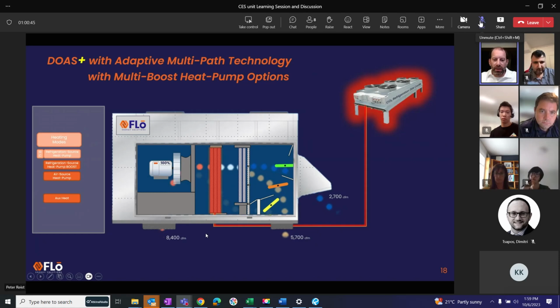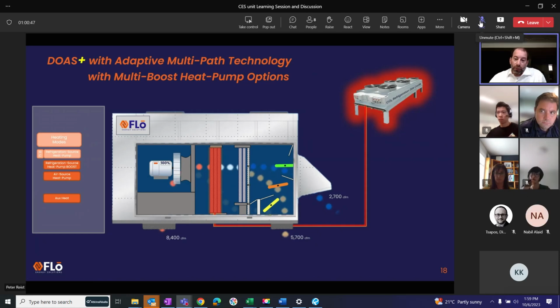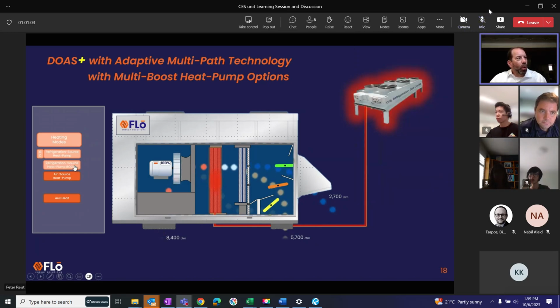It might still be, even in this project, a first stage of heating, because it's okay on its own. But what happens often is, in some of our systems, you guys will do some CO2 projects with other customers. I know Dave Bradley does. We have the opportunity in some of those projects to even get more heat. We can go as far as almost getting all of the heat that would otherwise go up to the roof to the condensing unit of the refrigeration system, and put it through our unit.